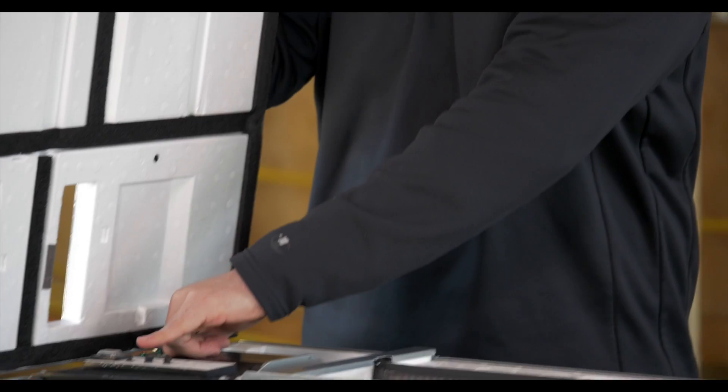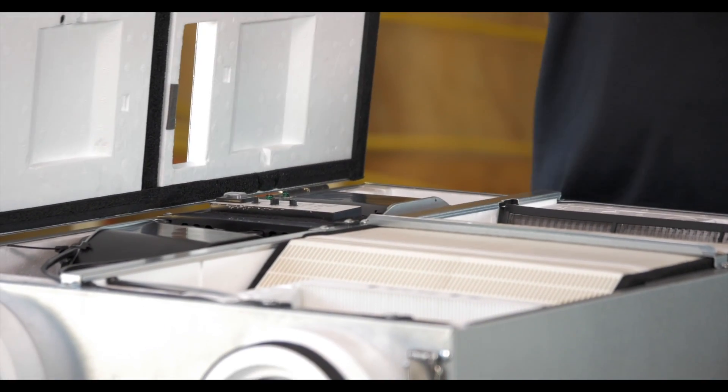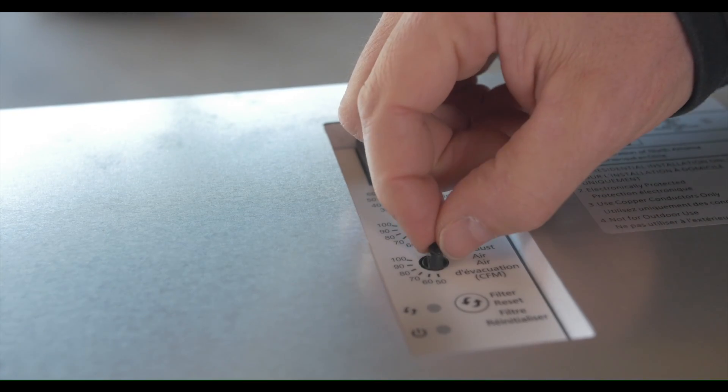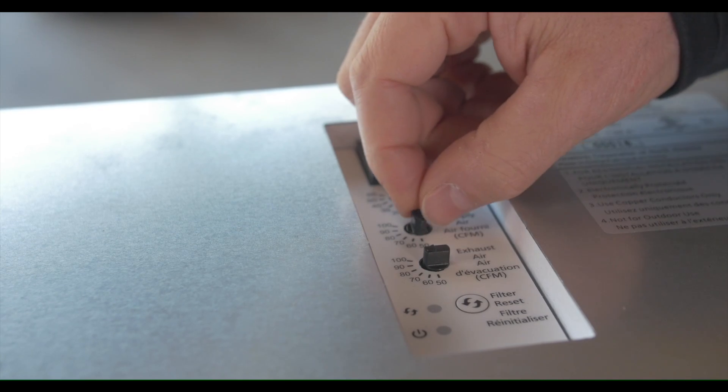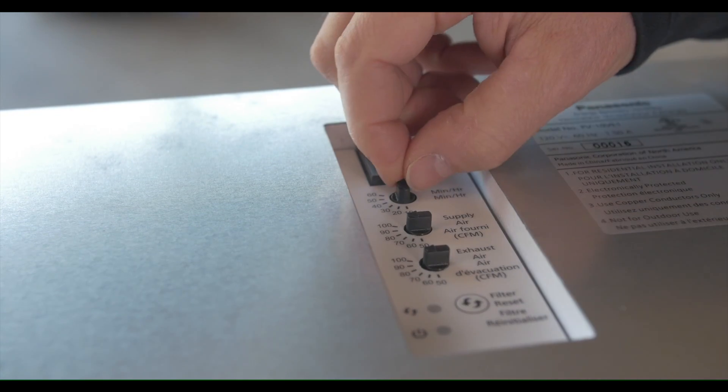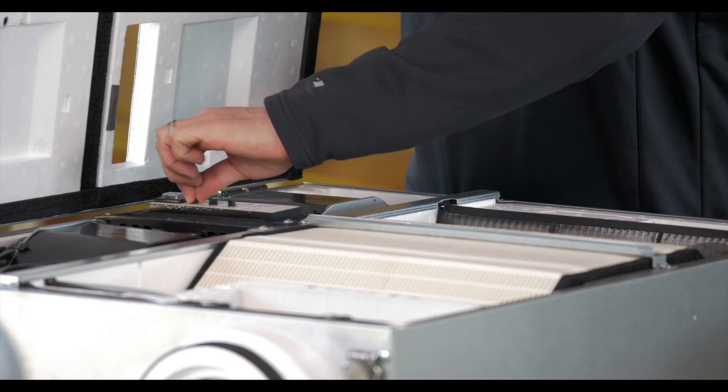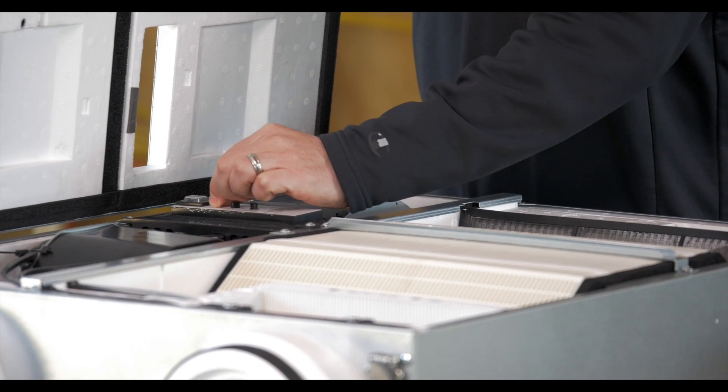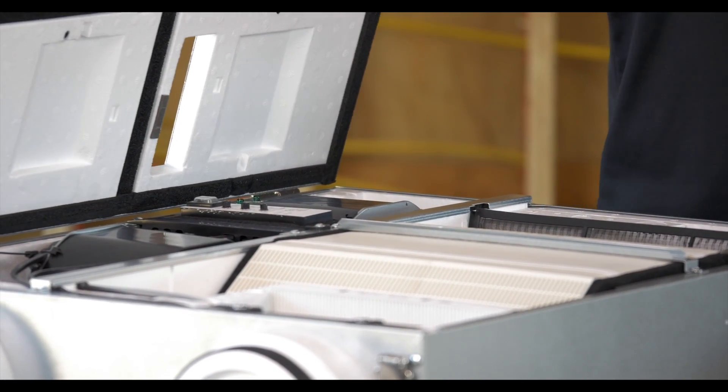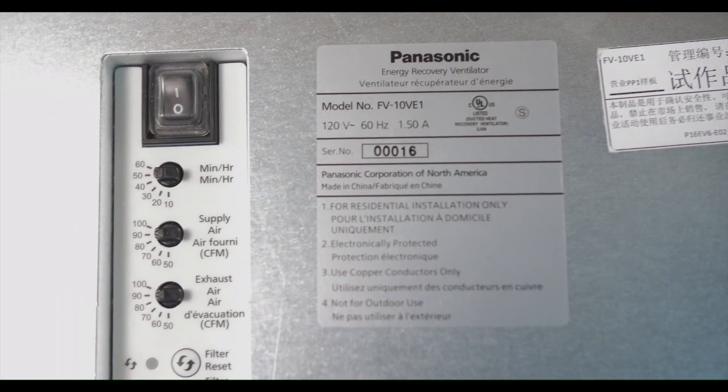The other thing that it's got on here is this timer system. This is going to help you meet that code by varying the amount of time this fan is going to run over the course of an hour. We can click this right here and it can go from 10 minutes per hour anywhere up to 60 minutes an hour in 10 minute increments. A lot of adjustability.